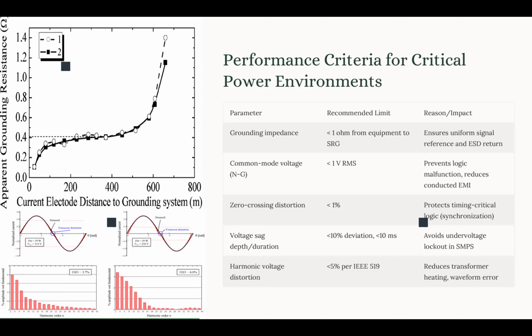Okay. Now, we already mentioned we have some parameters named common mode voltage, which is the voltage between the neutral and ground at the input terminal of our equipment. Now, the recommended limit for that parameter is that the voltage between neutral and ground should be less than 1 volt RMS. This is measured at the input terminal of the equipment.